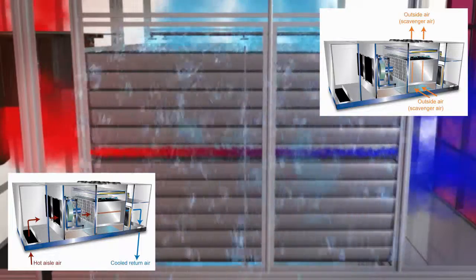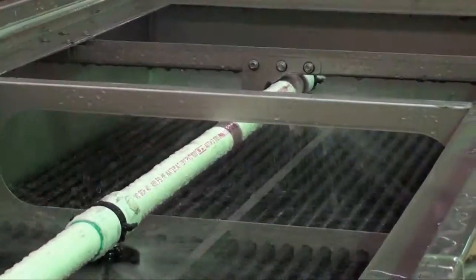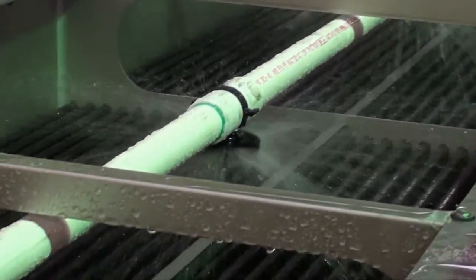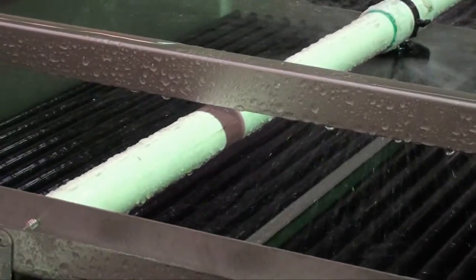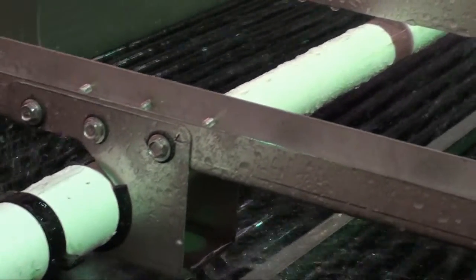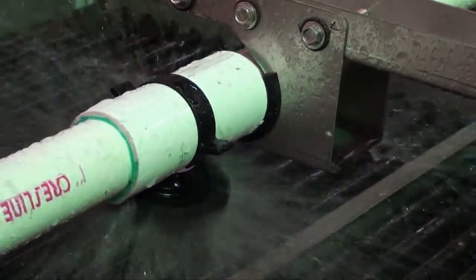And you can evaporatively cool that air in the summertime or whenever it gets above a certain temperature so that you don't have to turn on your mechanical cooling until kind of a last resort. So we don't have to turn on our mechanical cooling until the hottest of the summer afternoons. Otherwise, we're either running through a dry heat exchanger or we're running through a wet heat exchanger with evaporative cooling. If there's dust in the air from a farmer, if there's smoke in the air from fields burning or whatever may be going on, none of that gets into our data center. We're keeping our servers cool and we don't have to worry about contamination.